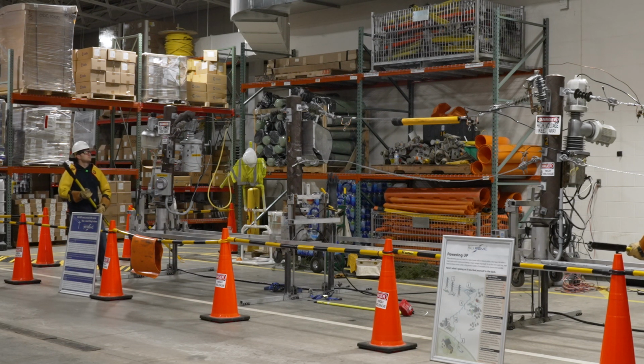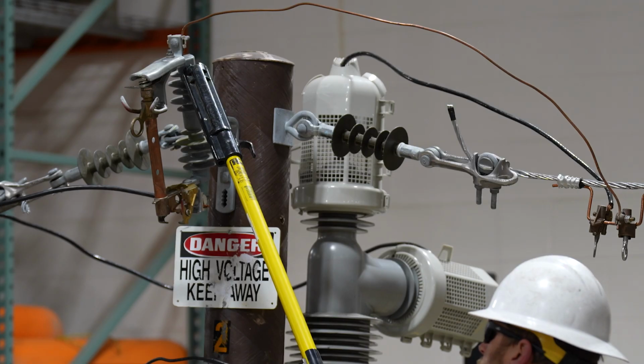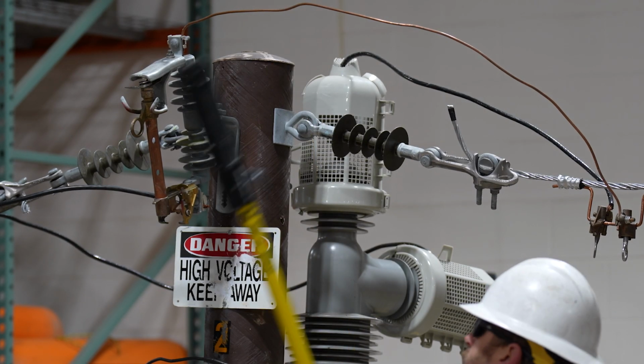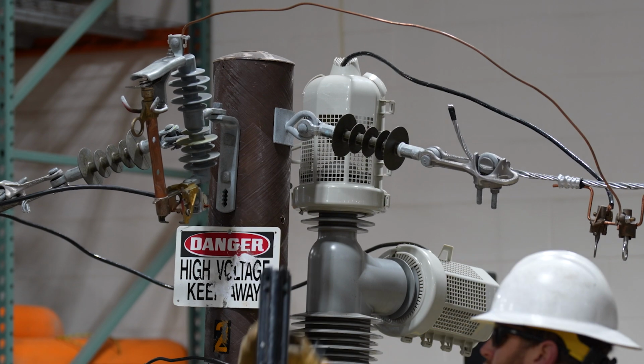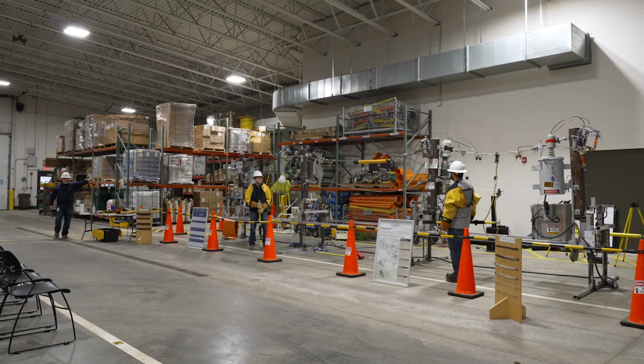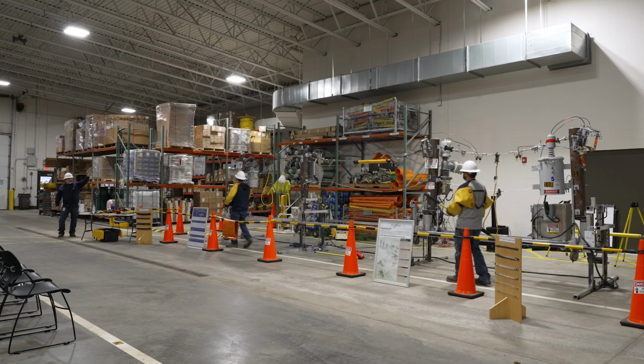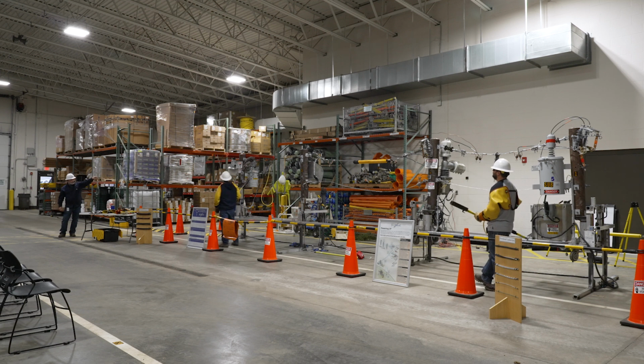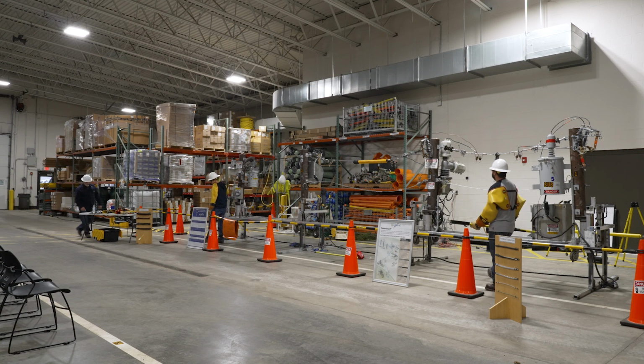Now, some of the equipment we have on the pole: when you hear us talking about cutouts, it's these devices here. Those are generally what we have at our transformers, some of our line taps. So if we have a fault, a tree, a squirrel, whatever, a lot of times those will open because they're a one-time use type operation. As soon as it blows, it drops open and we have an outage. And we'll come out and repair that outage.